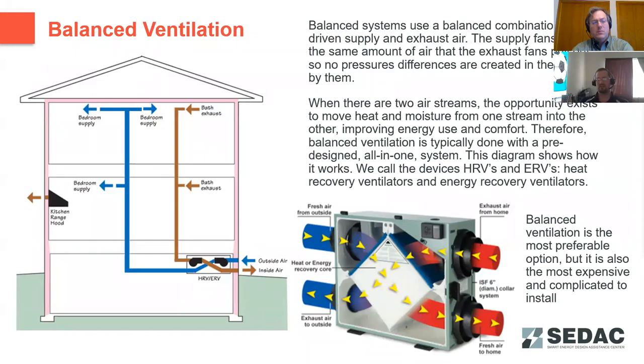Probably the second most common, just because of the efficiency gains you get from it, is the balanced ventilation system. You've got an exchanger, either in a crawl space, a mechanical room, up in the attic, that is exchanging heat, and for a full energy recovery one, it's also exchanging moisture between the exhaust air and the incoming outside air, so that you're minimizing how much you're having to condition that air and minimizing the energy that the HVAC system needs to consume. This is the best method for doing ventilation in a building because it minimizes the risks the other 2 methods have as far as pushing air through leaks in your building envelope. And it also minimizes the long-term energy costs for the client.